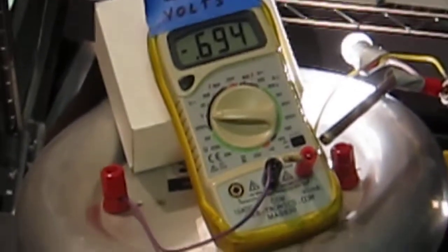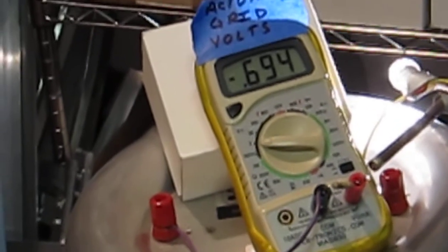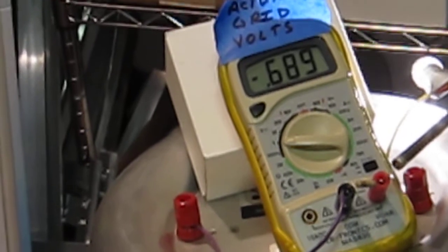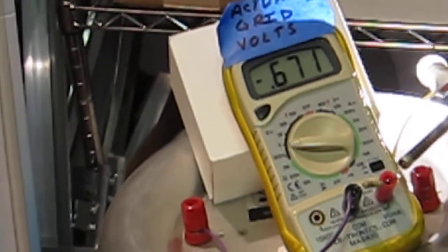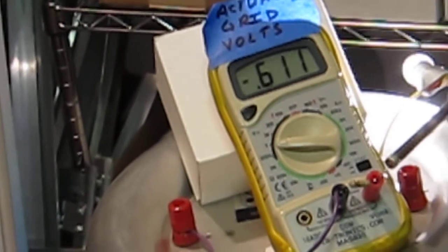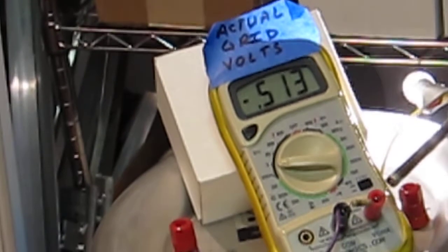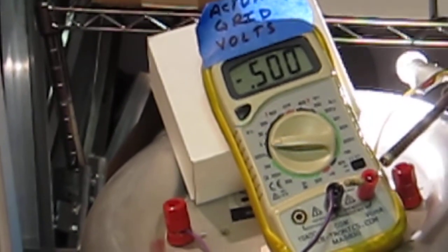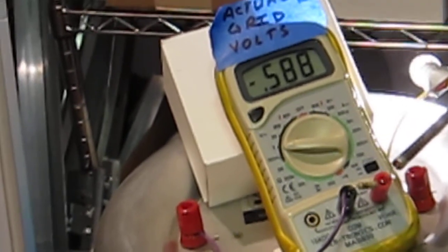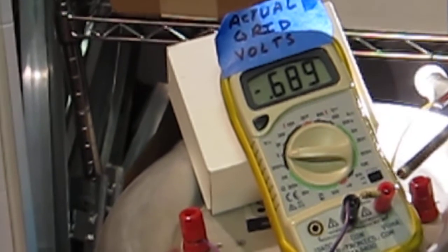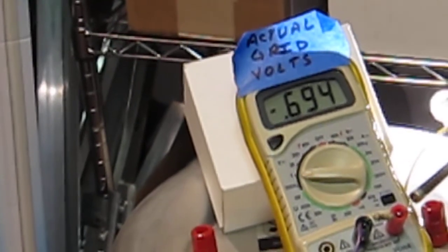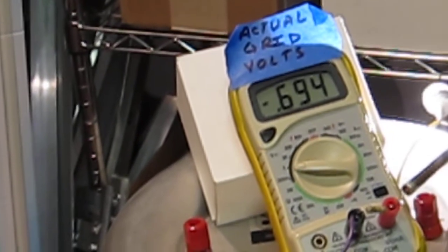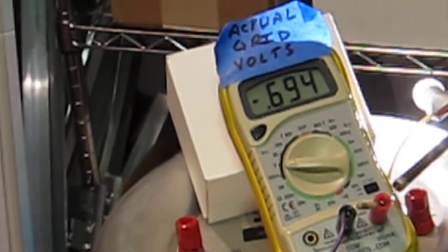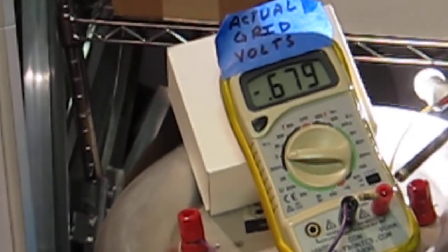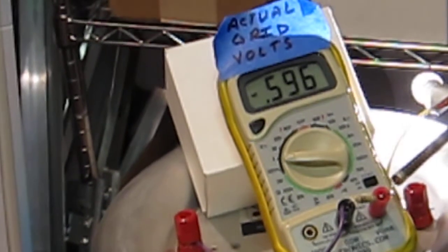And then if I adjust the tube current, the circuitry in the XRG-160 is going to try to servo the tube current by adjusting the grid voltage, but it won't be able to do it properly. All I can demonstrate to you here is that the XRG-160 is trying to servo. So it's hunting, trying to make the X-ray tube behave properly. And you'll be reminded that the tube current in this type of X-ray tube, the fine focus X-ray tube, is not determined by the filament current, it's determined by the grid voltage. So this is the control where the X-ray tube current is being controlled.